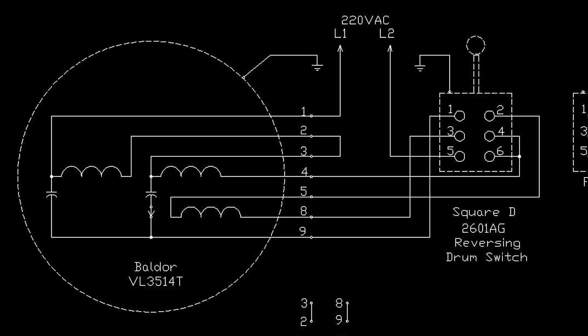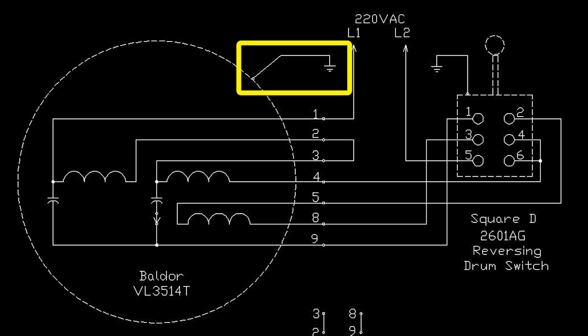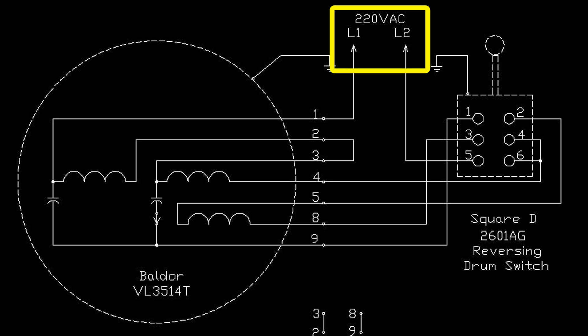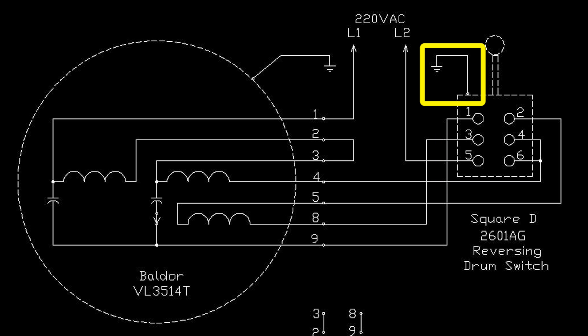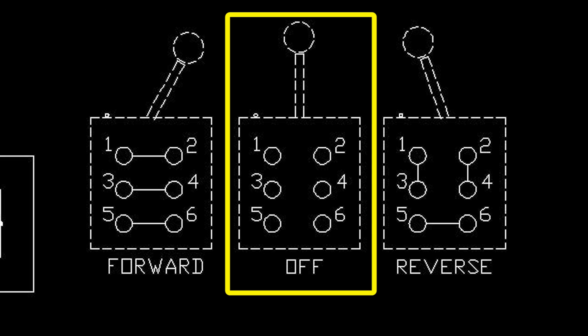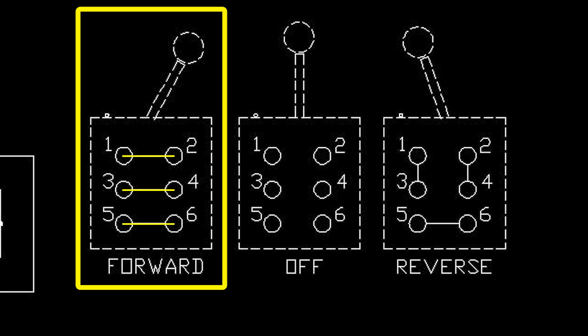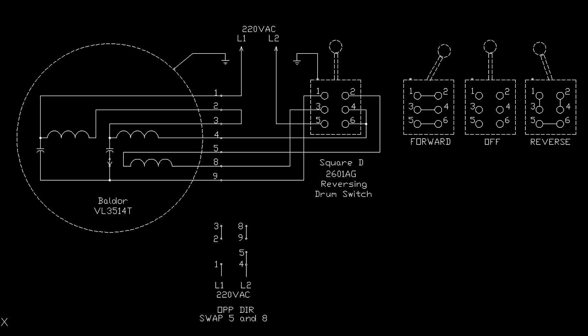Here's my simple wiring diagram. This is the motor — always make sure you have a good ground connection. These are the motor leads. The power source I'm using is 230 volts AC. This is the Square D 2601AG reversing drum switch and it has a ground connection also. Here's the drum switch in the off position — no contacts are made. Handle in reverse, these contacts are closed. Handle in forward, these contacts are closed. Pause the video as needed to take a better look at the drawing.